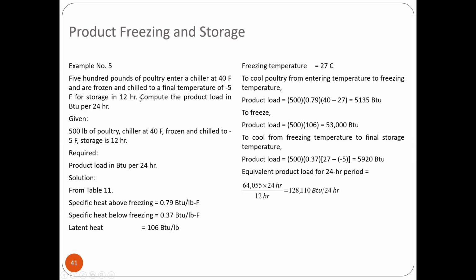So example number 5, 500 pounds of poultry enter a chiller at 40 Fahrenheit and are frozen and chilled to a final temperature of -5 Fahrenheit for storage. So storage is in 12 hours. Compute the product load in BTU per hour, 24 hours. So given 500 pounds of poultry, chiller at 40 Fahrenheit, frozen and chilled to -5 Fahrenheit, storage is 12 hours. Required product load in BTU per 24 hours.